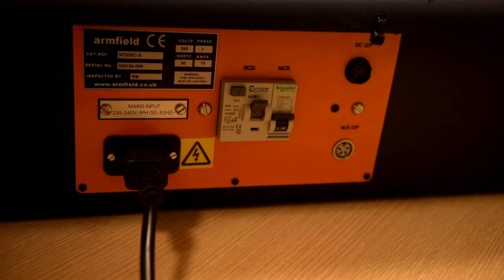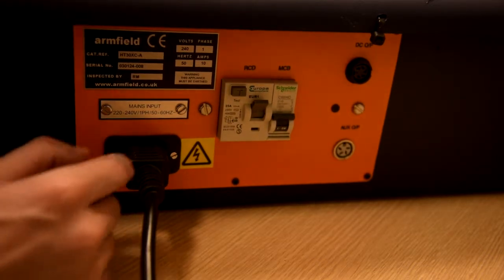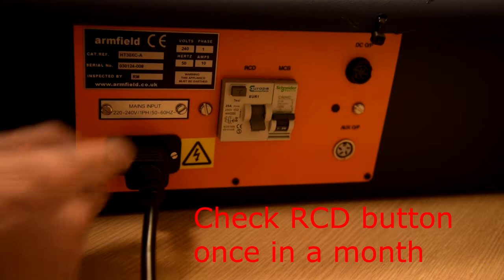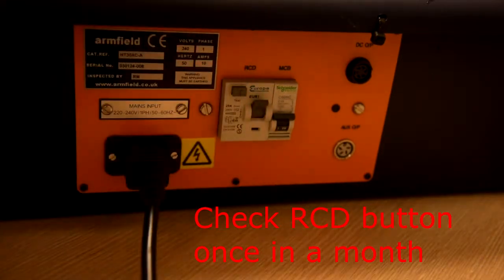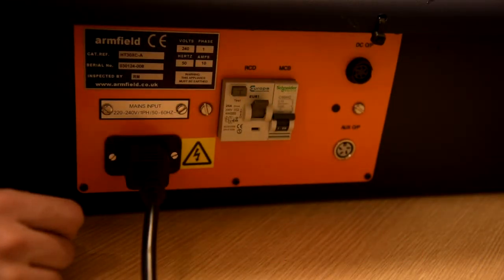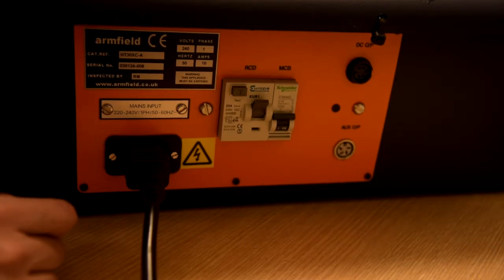Also, once a month you should check this RCD button. This should be triggered. If not, then do not use this equipment. This is pretty much the end of the video instruction. Thank you for watching.